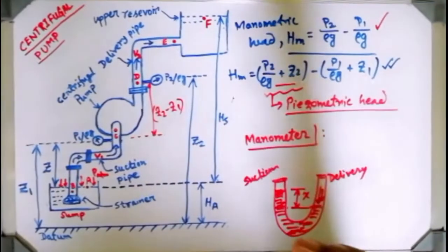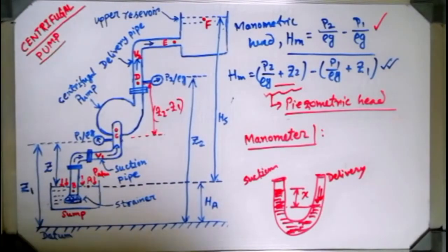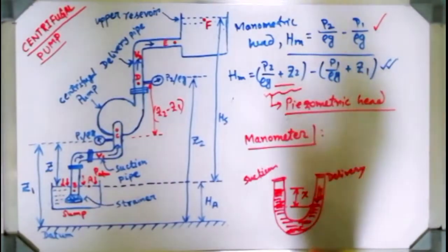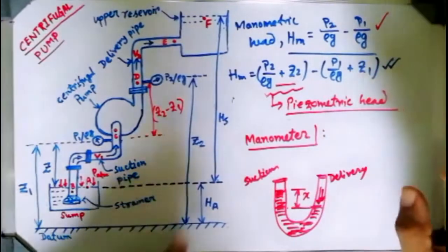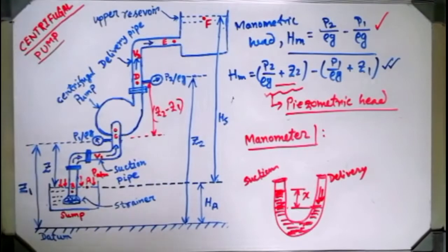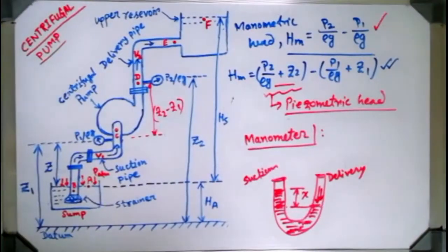Now why am I saying this is manometric head? Because if we connect a manometer at these two suction and delivery points, we will get these values directly. Again repeating, if you connect this manometer here, the head difference you get will give you this total value directly, because this manometer actually gives us the difference of piezometric head.